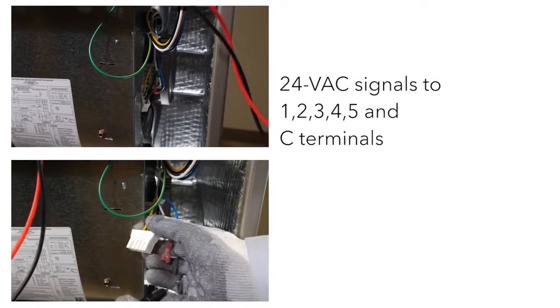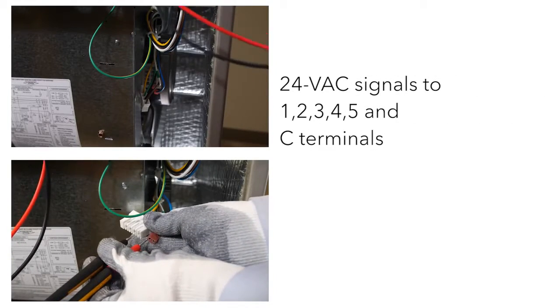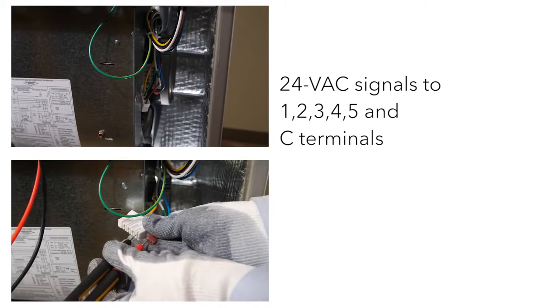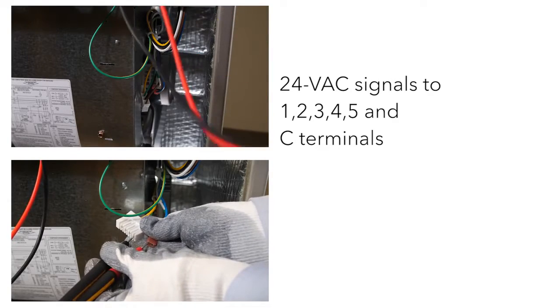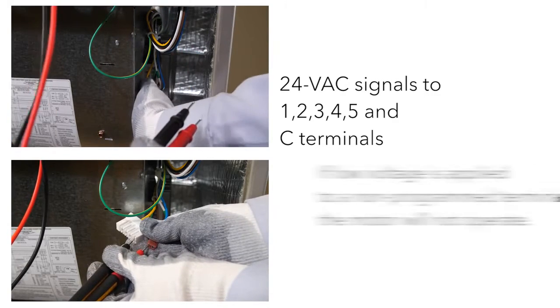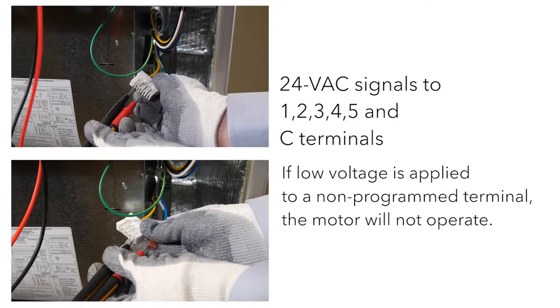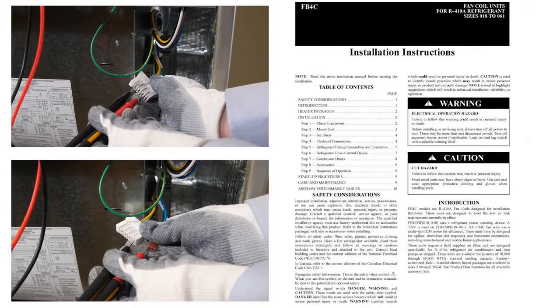The motor is communicated through 24 VAC signals to the 1, 2, 3, 4, 5 and C common terminals. Not all taps are programmed. If low voltage is applied to a non-programmed terminal, the motor will not operate, which is normal. Check the published literature of the unit for airflow delivery tables to see which speed taps are programmed.